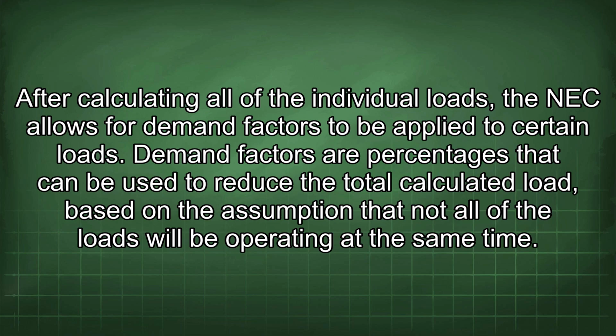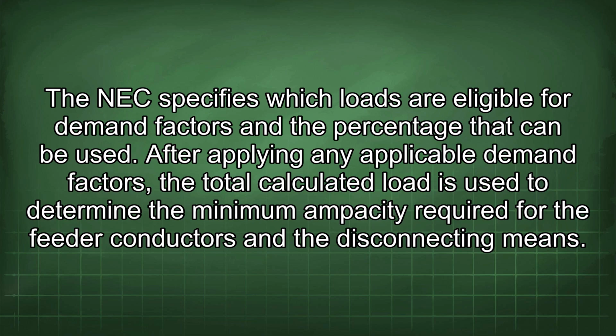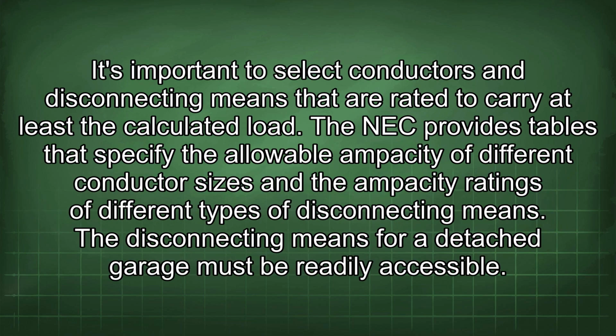After calculating all of the individual loads, the NEC allows for demand factors to be applied to certain loads. Demand factors are percentages that can be used to reduce the total calculated load, based on the assumption that not all of the loads will be operating at the same time. The NEC specifies which loads are eligible for demand factors and the percentage that can be used. After applying any applicable demand factors, the total calculated load is used to determine the minimum ampacity required for the feeder conductors and the disconnecting means. It's important to select conductors and disconnecting means that are rated to carry at least the calculated load. The NEC provides tables that specify the allowable ampacity of different conductor sizes and the ampacity ratings of different types of disconnecting means.